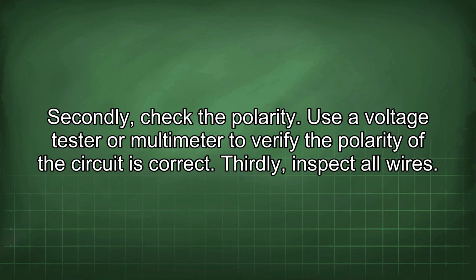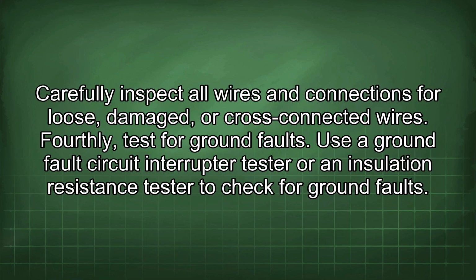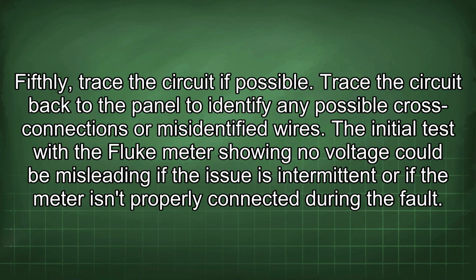Secondly, check the polarity. Use a voltage tester or multimeter to verify the polarity of the circuit is correct. Thirdly, inspect all wires. Carefully inspect all wires and connections for loose, damaged, or cross-connected wires. Fourthly, test for ground faults. Use a ground fault circuit interrupter tester or an insulation resistance tester to check for ground faults. Fifthly, trace the circuit if possible. Trace the circuit back to the panel to identify any possible cross connections or misidentified wires.